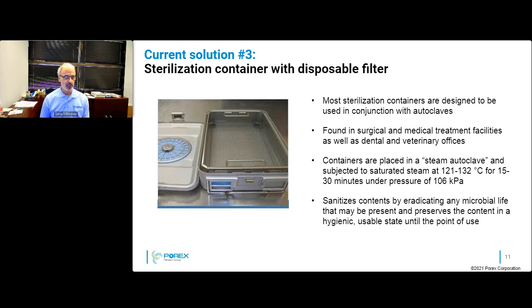They are typically autoclaved and exposed to saturated steam at 121 to 132 C for about 15 to 30 minutes under a pressure of about 106 kilopascals. So it's slightly above atmospheric pressure, and it sanitizes by eradicating any microbial life. So these are truly sanitized products. So this is really the method of choice for most hospitals and clinics. It's very efficient and very repeatable and very sustainable.